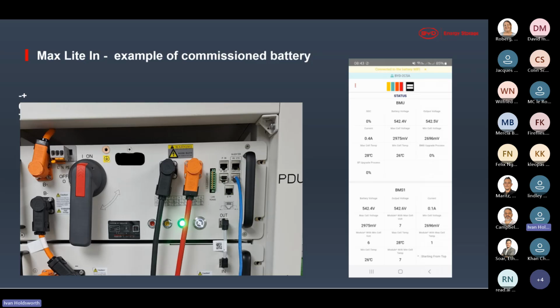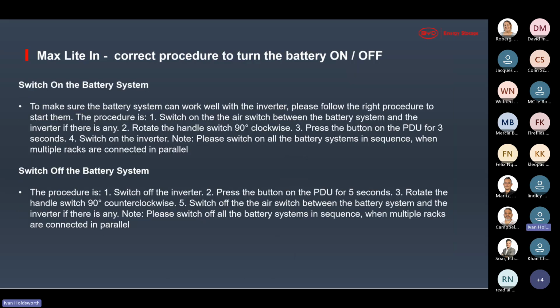And here we can see an example of an installed battery, and where your communications go. That's a single tower, so you can see the termination resistor in P out, and your communications to the inverter in the CAN bus port. And then that's the turn on procedure: essentially making sure all your fuses are closed before turning on, and then, when your inverter and your batteries are off, rotating your switch to the on position, and then turning on your battery with the LED button.